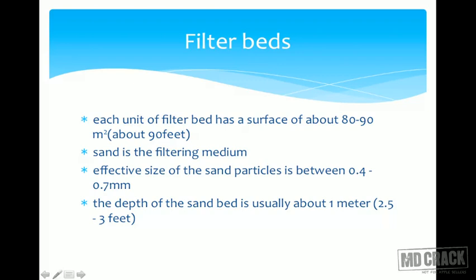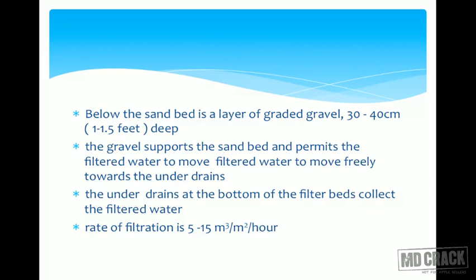The depth of the sand bed is usually about 1 meter — about the same as in the slow sand filter. Below the sand bed there is a layer of graded gravel, 30 to 40 centimeters deep, also about the same as the slow sand filter. The gravel supports the sand bed and permits filtered water to move freely towards the under drains, which collect the filtered water. Basically, this filter box of the rapid sand filter is almost the same as that of the slow sand filter.